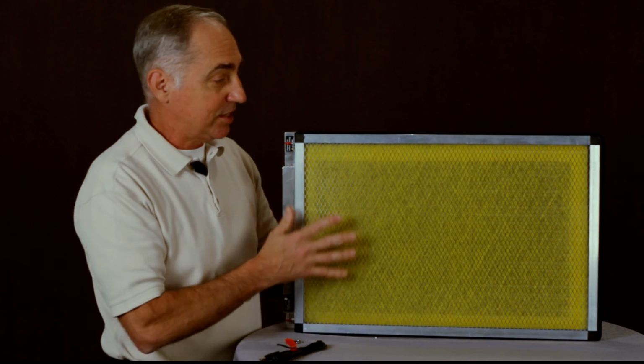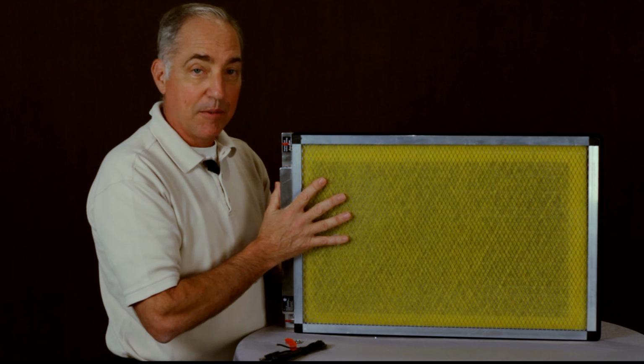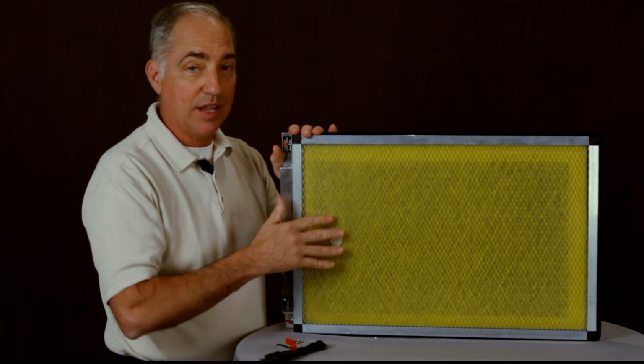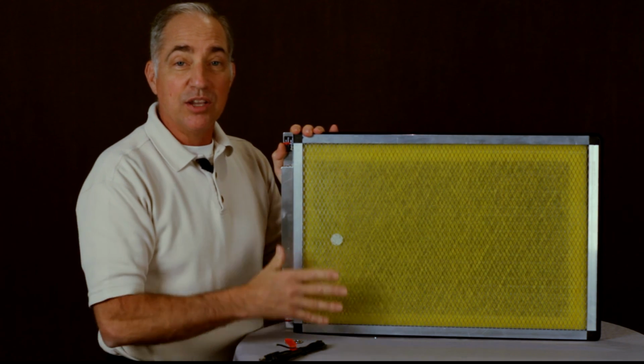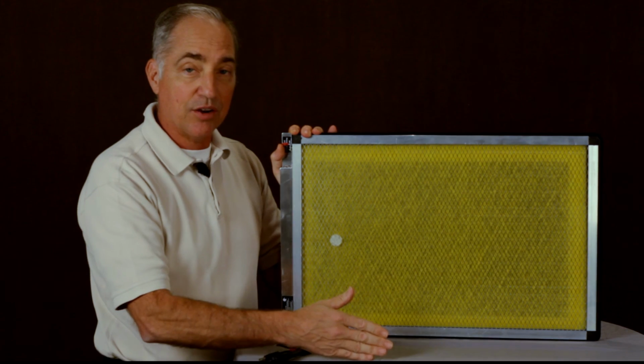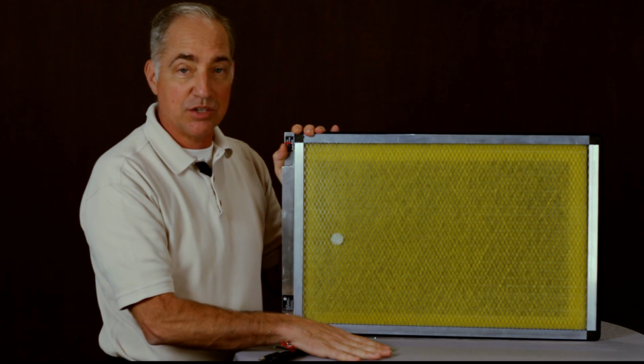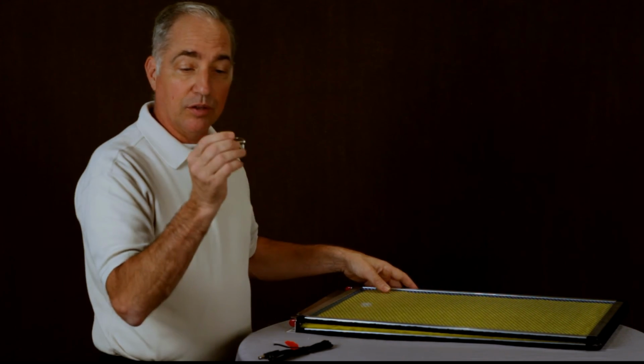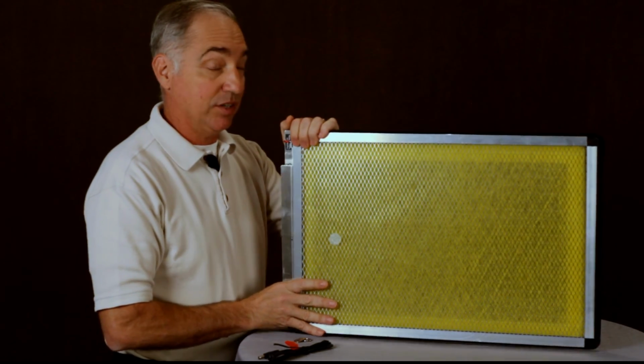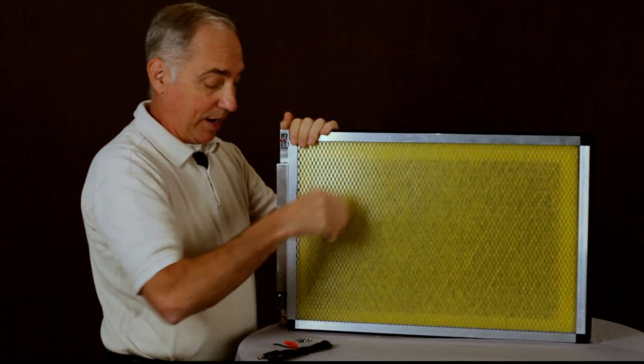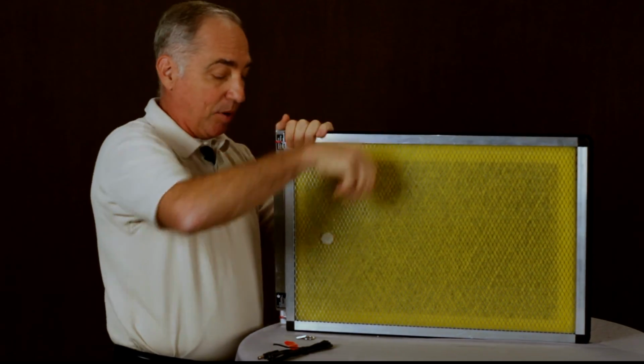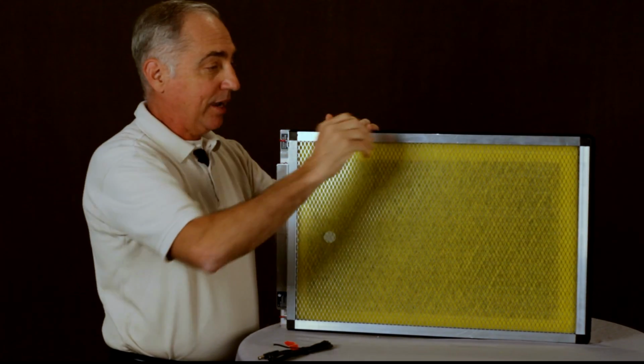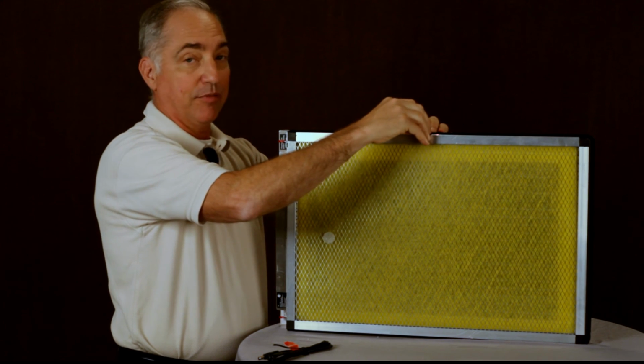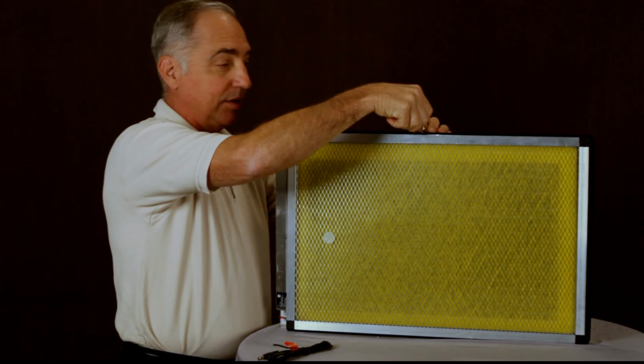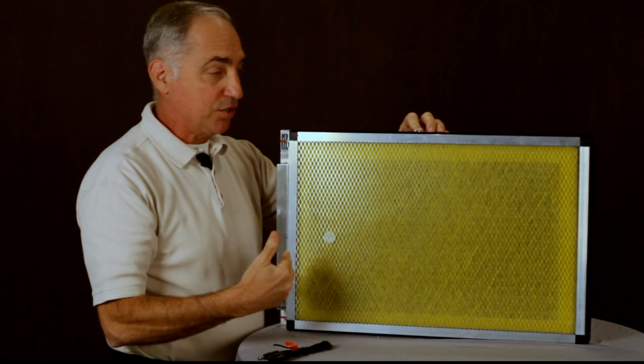So we have 40 standard sizes. This happens to be a 16x25, our most popular size. The other sizes are 20x25s, 20x20s, 16x20s, and here again, we have 40 different standard sizes and some strange sizes that we make for our southern markets as well. All standard, all the same price, and we can custom make just about any size you want. Another little option we have here is this little ring. There's about 30% of the time we have to drop these into a filter rack, and it's difficult to get it out unless you take a pair of pliers or something. So what you can do is it comes in every pack. You just have the little screw that comes in and you screw one of these onto the frame itself. And then now you've got a little hook to pull it out with. So that's a nice little feature for those applications where it's going to be more difficult to remove.